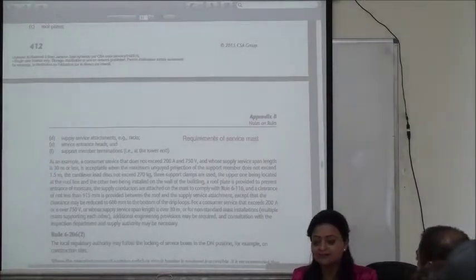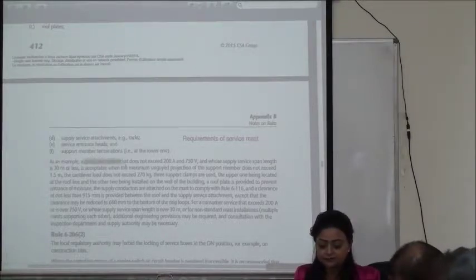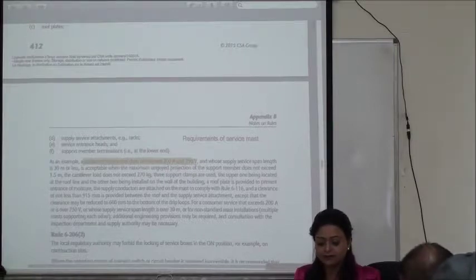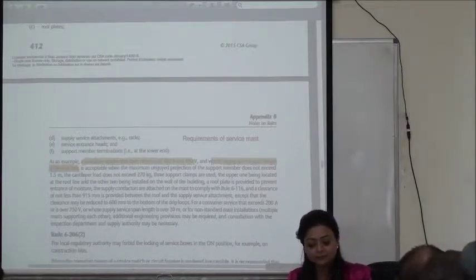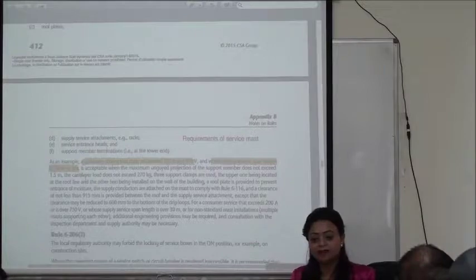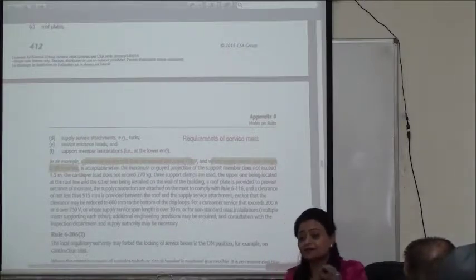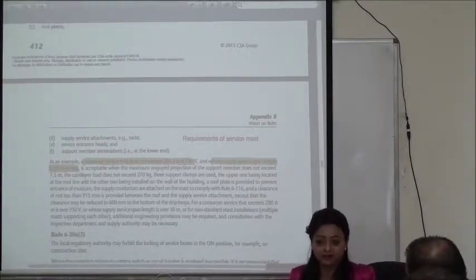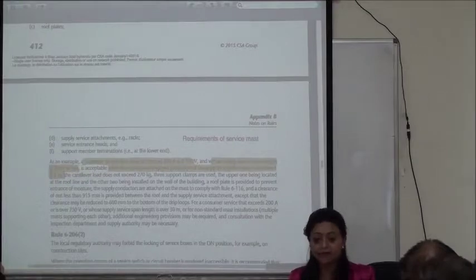What shall be the maximum capacity and voltage a consumer service can go up to? A consumer service cannot exceed 200 amps and 750 volts. What's the maximum length of the supply conductor for service? 30 meters. When the maximum unguyed projection of a support member exceeds 1.5 meters, the pole needs a guy wire. So anything beyond 1.5 meters needs a guy wire. A recurrent exam question: the maximum length of service wire is 30 meters.